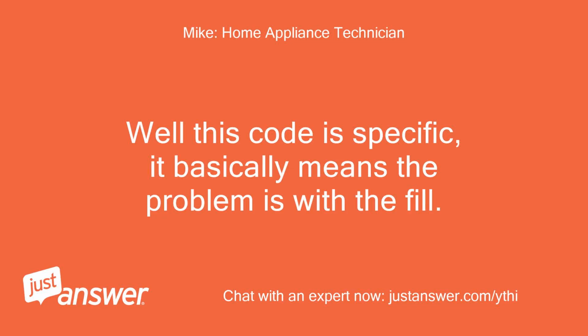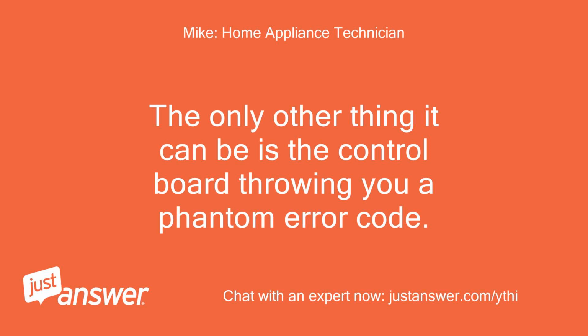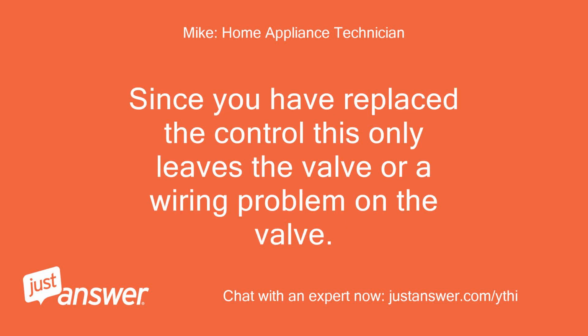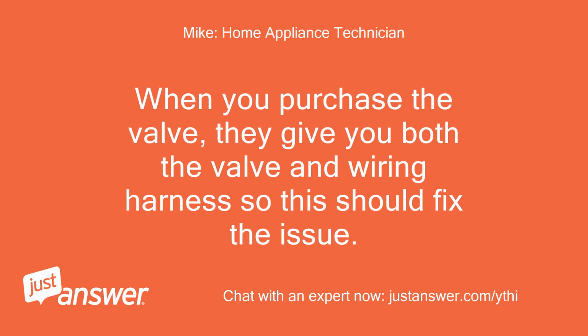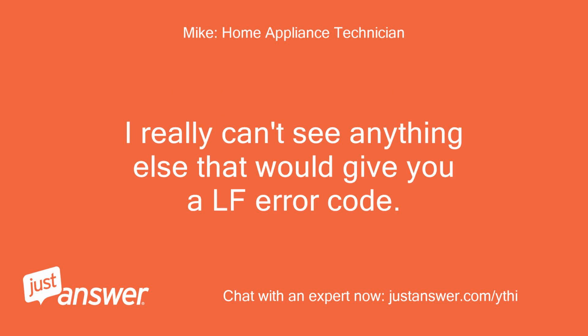Well, this code is specific. It basically means the problem is with the fill. The only other thing it can be is the control board throwing you a phantom error code. Since you have replaced the control, this only leaves the valve or a wiring problem on the valve. When you purchase the valve, they give you both the valve and wiring harness, so this should fix the issue. I really can't see anything else that would give you a LF error code.